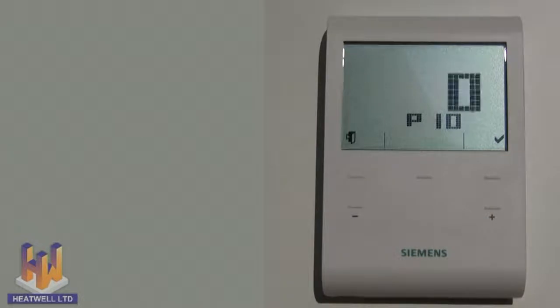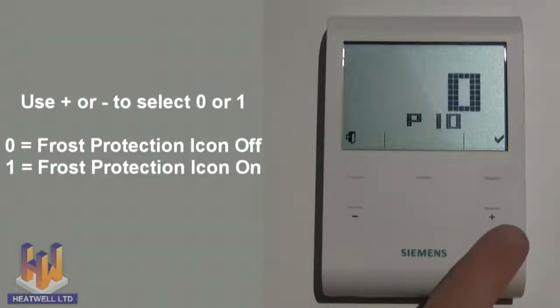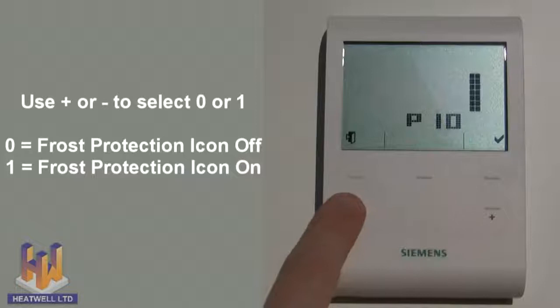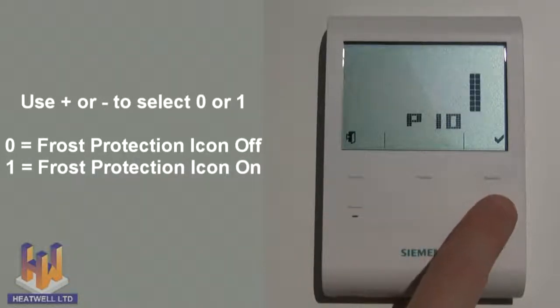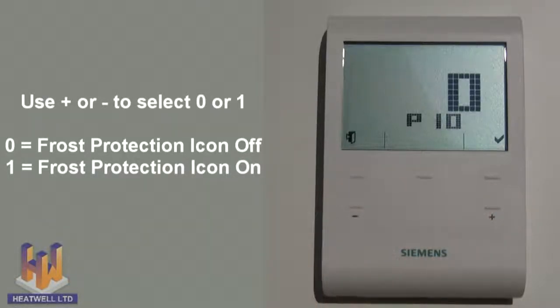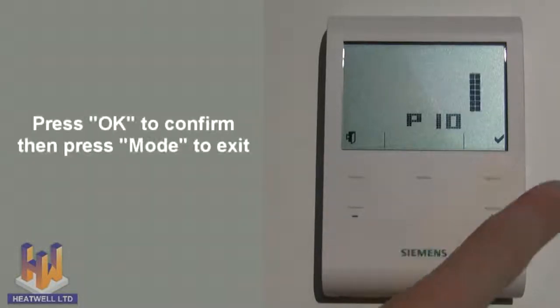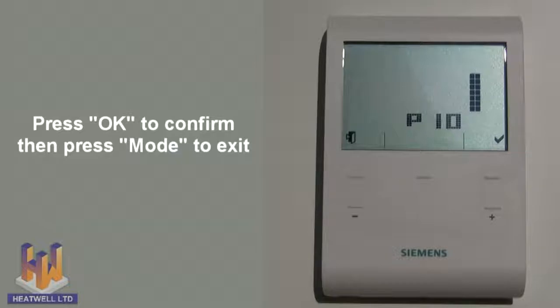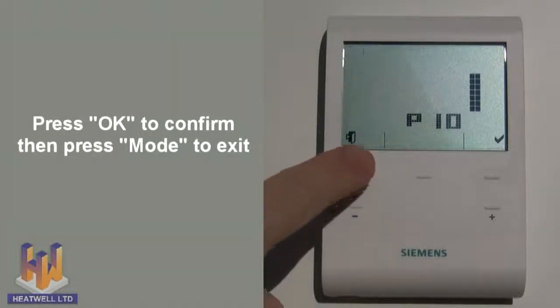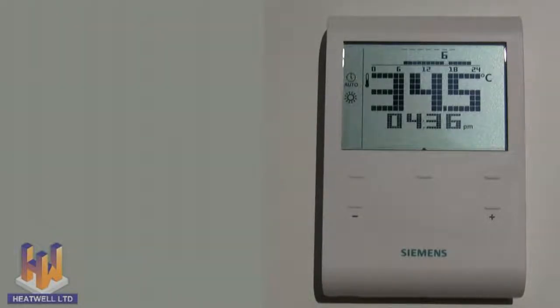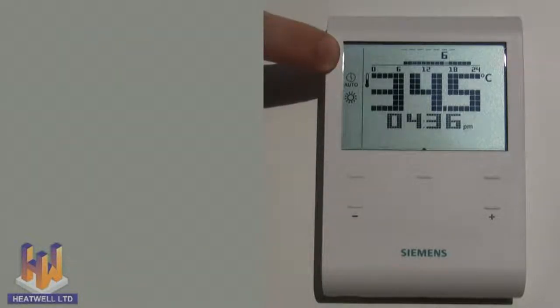Now use the plus or minus button to change between 0 and 1. 0 means the frost protection icon will not show, and 1 means the frost protection icon will show. In this case, we will select 1. Press OK to confirm, and then press the mode button to exit. The off or frost protection icon will now show when the unit is activated by very low temperatures or turned off.